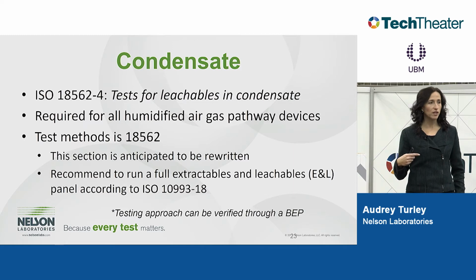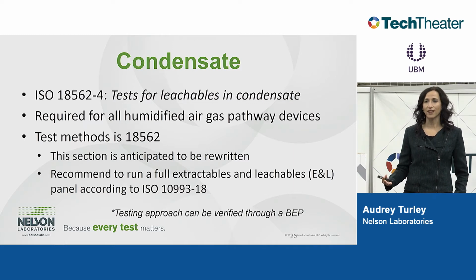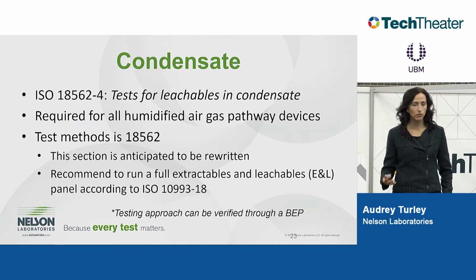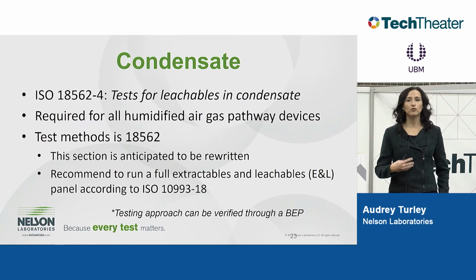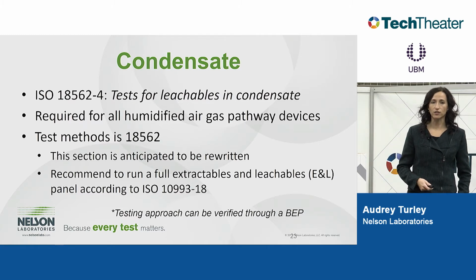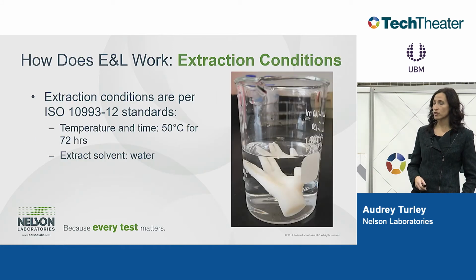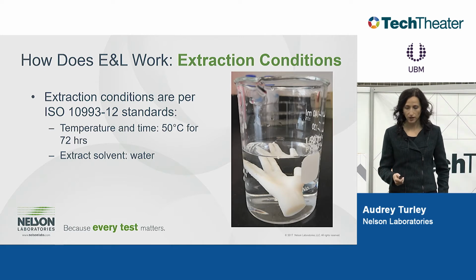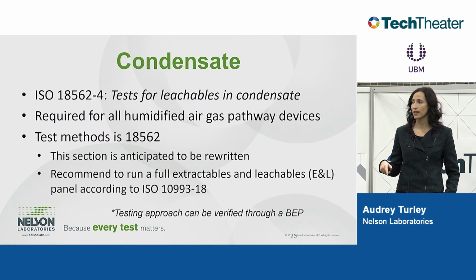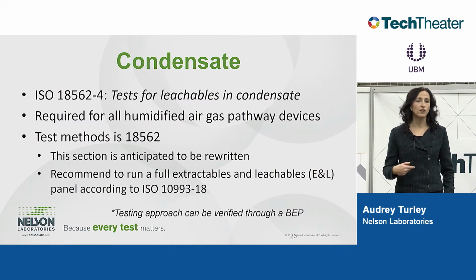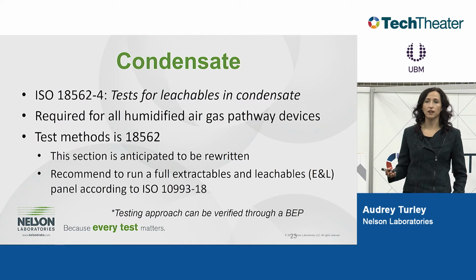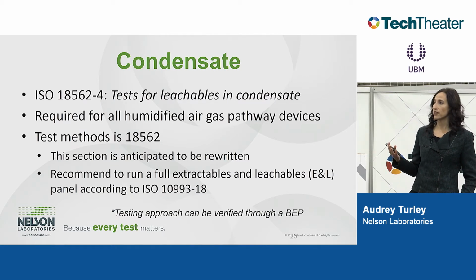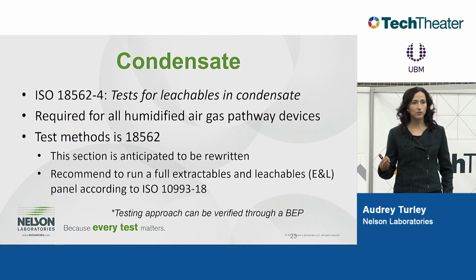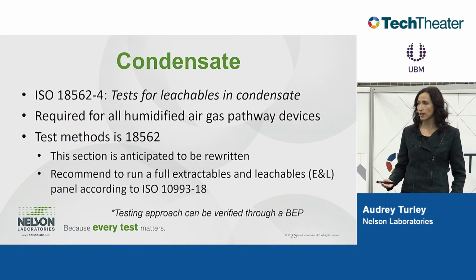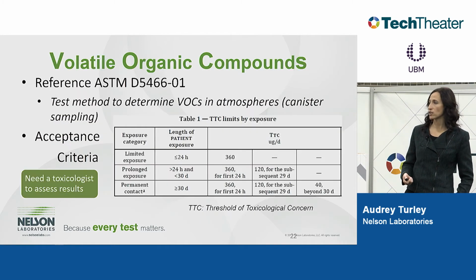So one thing we like to really promote here is to make sure you put this testing plan together and take it to the agency in a pre-sub, because there is so much disagreement in the agencies right now. You should get some forethought going before you start doing all of your testing. Save yourself some time and money in the long run. So I just want to talk a little bit about how extractables and leachables work. One thing I forgot to mention is when we assess the condensate, our typical recommendation is to do extractable and leachable. We call it a full panel, and I'll explain what that means. But instead of doing specific testing on a condensate that accumulates in the product, which is unrealistic, which is actually what's mentioned in Part 4, we recommend doing an extractable and leachables.